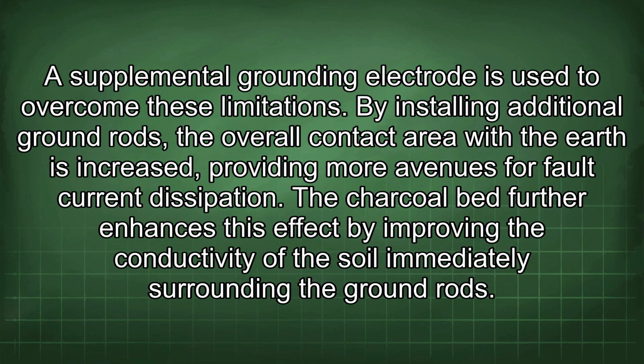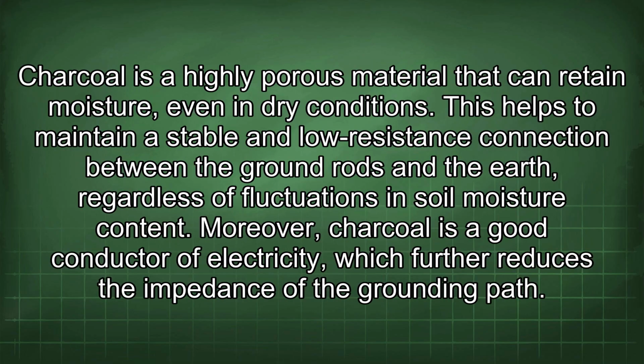A supplemental grounding electrode is used to overcome these limitations. By installing additional ground rods, the overall contact area with the earth is increased, providing more avenues for fault current dissipation. A charcoal bed further enhances this effect by improving the conductivity of the soil immediately surrounding the ground rods. Charcoal is a highly porous material that can retain moisture even in dry conditions. This helps to maintain a stable and low resistance connection between the ground rods and the earth, regardless of fluctuations in soil moisture content. Moreover, charcoal is a good conductor of electricity, which further reduces the impedance of the grounding path.